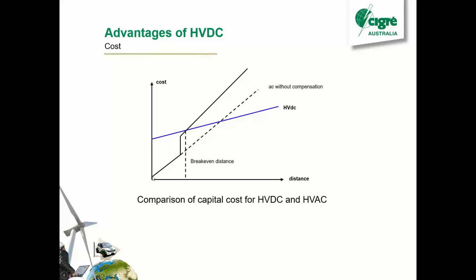So with AC, you start pretty cheap. You've just got to probably get a transformer, or maybe not even that, just a spare bay. And then this is the cost of your lines and your capitalized losses. If you add some series compensation, that can make it a little bit better, but again, you've got to pay for that series cap. So there is a point where HVDC will be cheaper. It's hard to put a number on it, but I'd have to say probably around 800 to 1,000 Ks you'd be getting there. There are other things to consider as well, but we'll go into those.